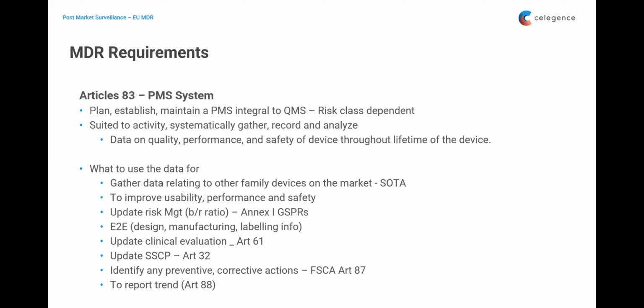You want to improve the usability and the performance and safety aspects, as I've just explained. You want to update your risk management file. Before going to market, you have defined your benefits and your risk ratios, which was guided by Annex 1 of your GSPRs, or Annex 1 of your essential requirements if you're a legacy device. You must be able to reevaluate all of these things as you're getting the complaints and the data coming through. You must be able to reevaluate some of these things and update your risk management file according to the current ISO standards, ISO 14971, 2019 version.